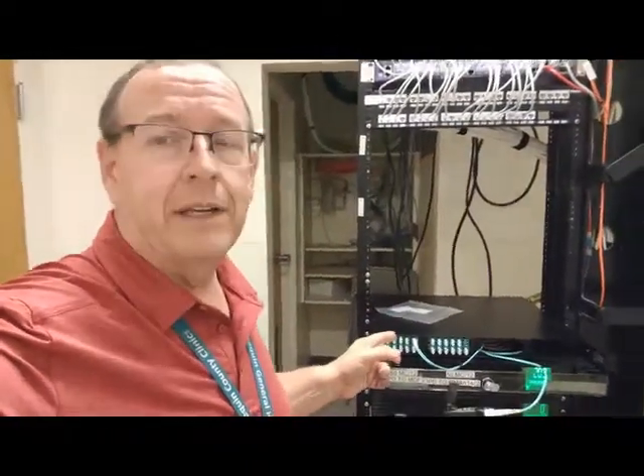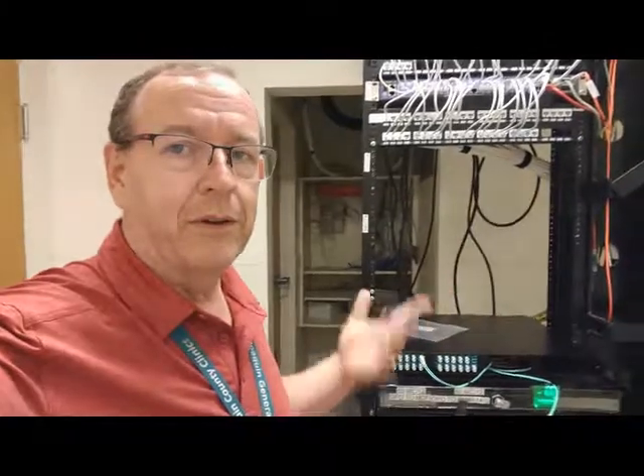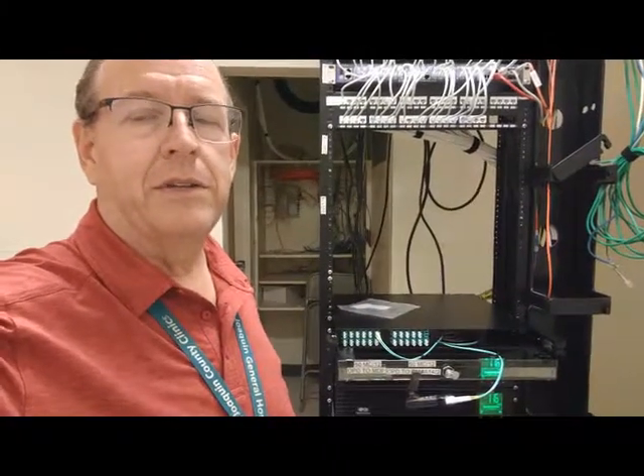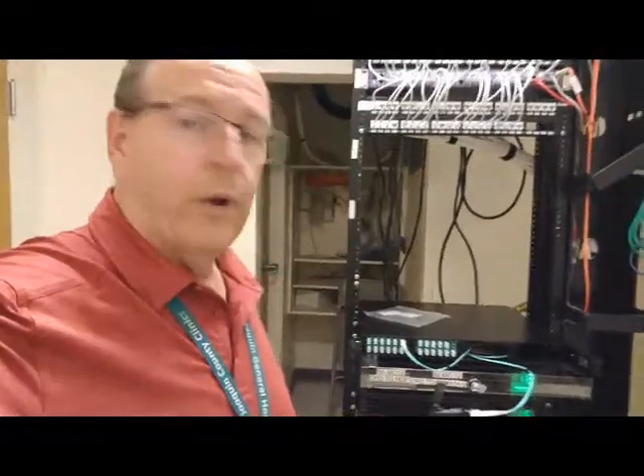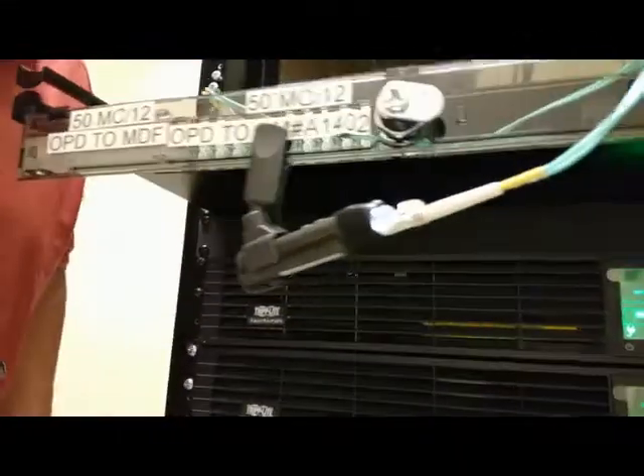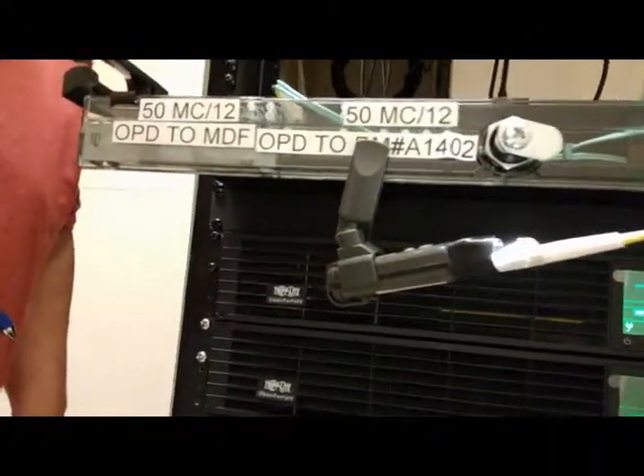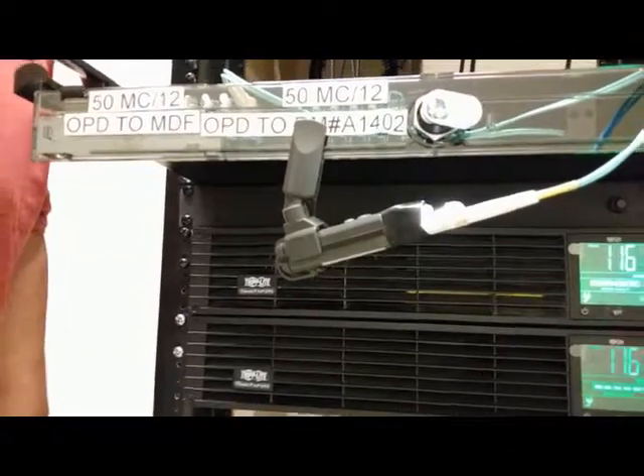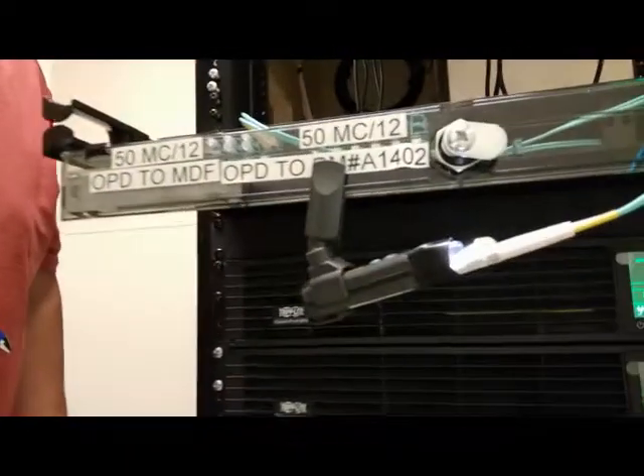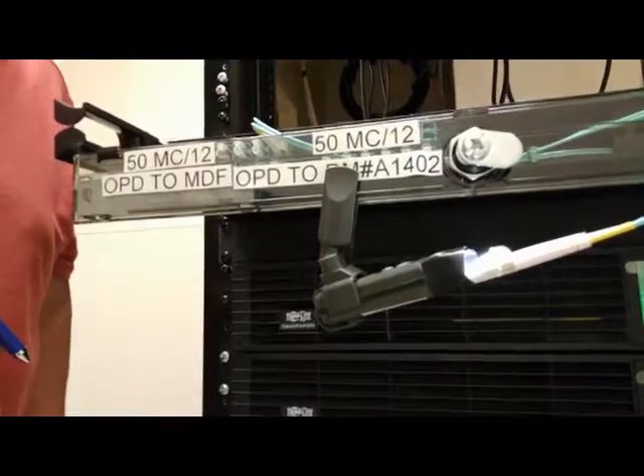I can pick up my cross connects, that's just great, but if I don't know where the fiber goes, I can't connect it up down in our MDF on the distribution switch. So what I do is connect up a very bright little flashlight to the fibers and shine a light through it. And then we will go down to the other end to try to find it.